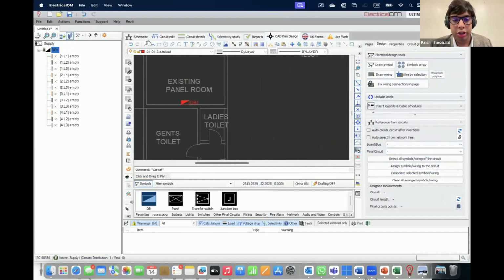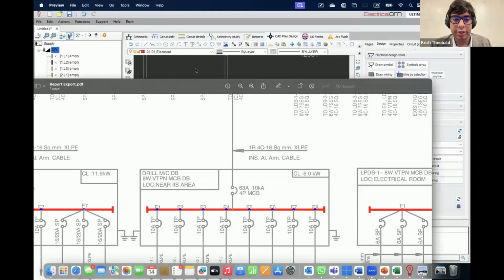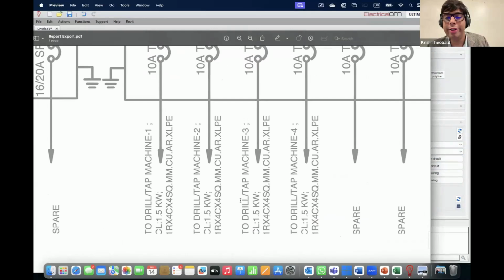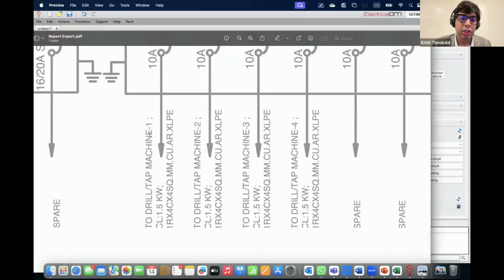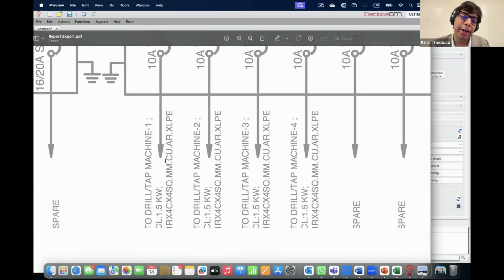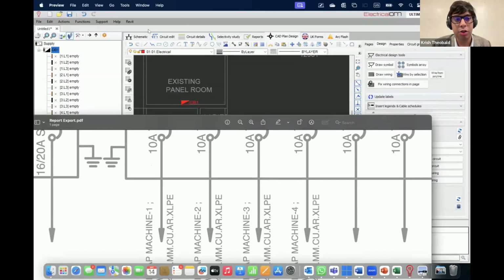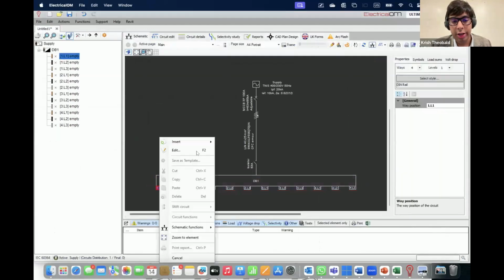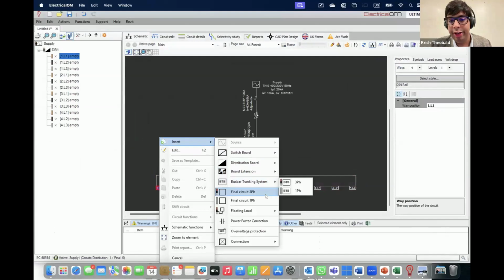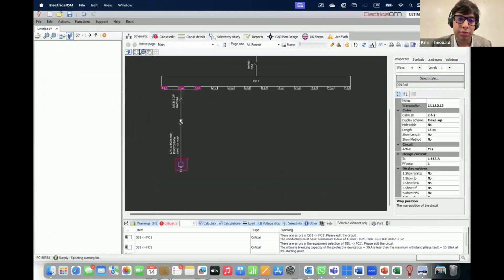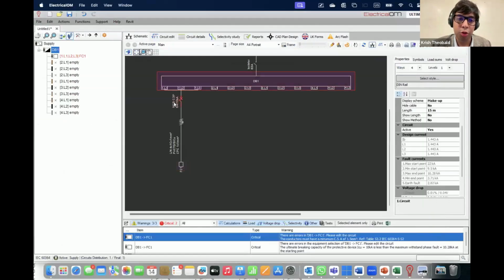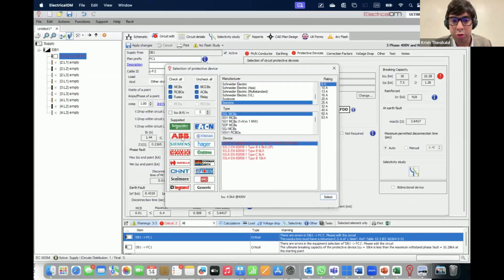Now, if we take a circuit, for instance, back to our SLD that we've got. So we've got some drilling tapping machines here, 1.5 kilowatts each. So say, for example, it's a 10 ampere MCB and 1.5 kilowatt load. This is saying use a 4 square mm copper armored cable. So let's do that. This is an insert. This would be a final circuit, 3-phase. So let's again look at our schematic. It's a 10 ampere three-pole MCB. So, for example, say you want a Siemens, uncheck MCB.